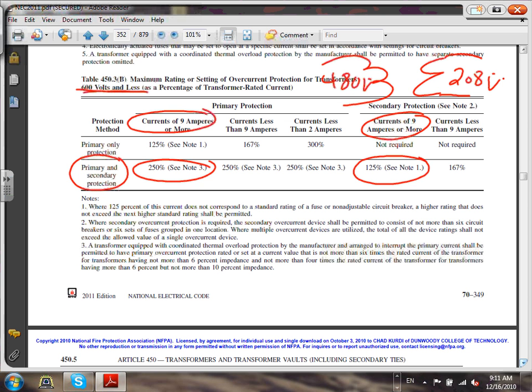Okay. I promise you guys, when you have, where would I use primary only protection? Taps. A good example of this, the 25 feet: you have a 480/277 panel here. You grab a 480/277 feeder to a transformer sitting here. From the transformer, 480 on this side, 208 on the other side, take the 208 to another panel. All of them are within 25 feet of each other. Then you don't have to have secondary protection right next to the transformer. Your secondary protection can be right inside the panel. They use it, guys, all the time. I promise you we'll do this whole exercise when we do the industrial more.